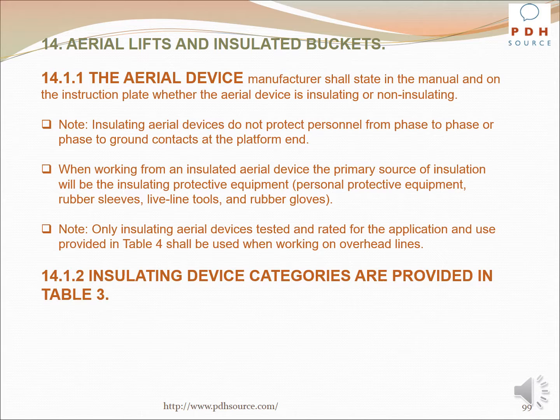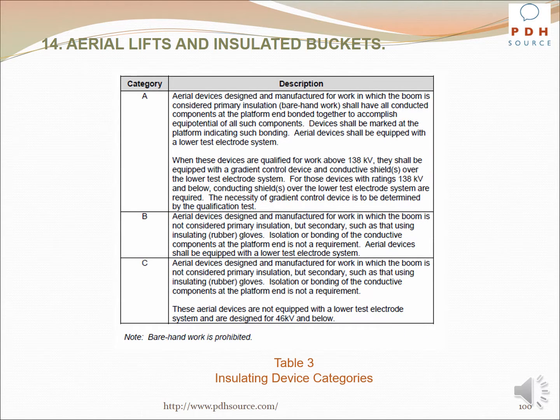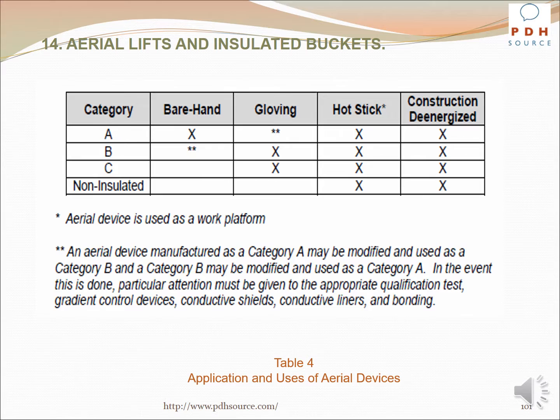When working from an insulated aerial device, the primary source of insulation will be the insulating protective equipment, personal protective equipment, rubber sleeves, live line tools, and rubber gloves. Note: only insulating aerial devices tested and rated for the application and use provided in Table 4 shall be used when working on overhead lines. Insulating device categories are provided in Table 3. This slide has Table 3, the insulating device categories A, B, C with descriptions as indicated. Table 4 indicates application and uses of aerial devices.